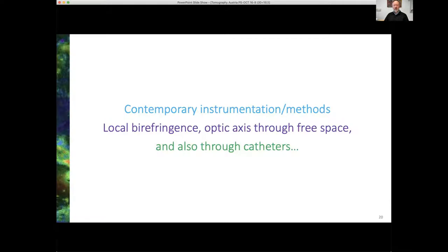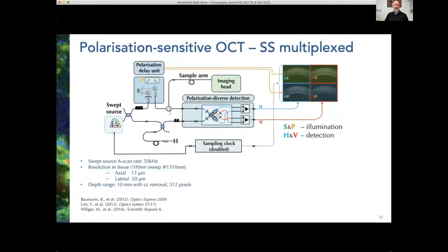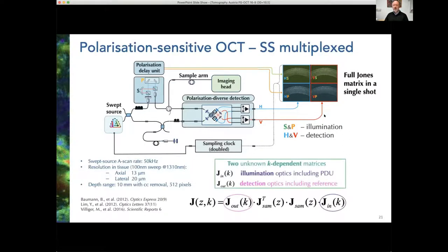I'm going to show you some contemporary instrumentation and briefly touch on how we extract local birefringence, noting that this can now be reliably done through catheters — which I think is another game changer. Here is a swept source OCT system. You can see the polarization delay unit and polarization diverse detection — these are the key things. We generate time-delayed S and P states in the polarization delay unit, then detect them with polarization diverse detection, generating an H and V channel, ending up with the four elements of a Jones matrix — captured in a single shot, which is rather beautiful.